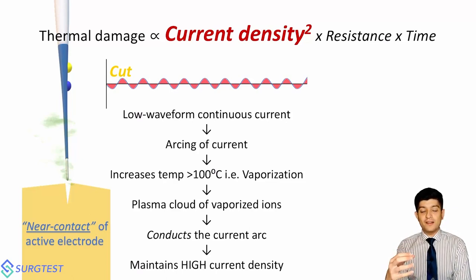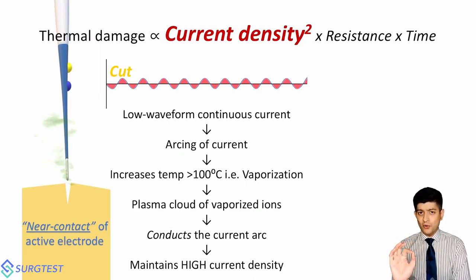So you're basically causing current arcing, but you're not doing it using the high voltage current present in a coag mode. Remember, I'm talking about a safe cut current which is present on screen. In a coagulating current with extremely high voltage, you will find sparking very, very easily. I'm going to show you one example in just a bit. That's because also remember that the coagulating current has an inbuilt spray mode. The spray mode is one of the highest voltage settings that you will have within the coagulating current, and it causes absolute sparking across tissues. You want the tissues to have some sparking, but you want to do it in a low voltage manner that maintains current density. So this, using the cutting current, is a very targeted application of energy to a narrow area.